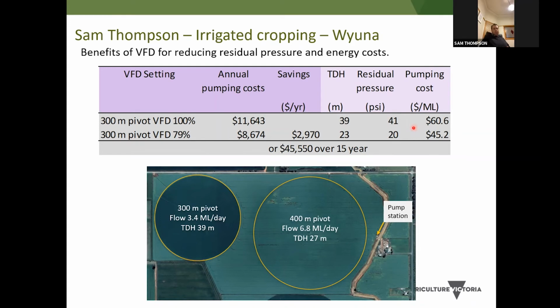So looking towards the future, we're looking at the three-phase power option, and if that is uneconomical, we may even look at things like a blended power situation with solar and batteries, so we can use the existing 2 phases that are already supplied to the farm.